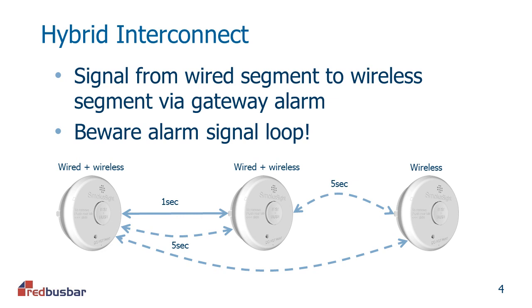However, for the wireless smoke alarm on the far right to sound, it's going to take about 5 seconds for it to receive the active alarm, and that's all fine. It will sound no problems. If at a later stage the originating alarm on the left-hand side stopped alarming, or the reason for it to alarm extinguished, for instance, then it would take a passage of time before the wireless alarm on the far right-hand side would stop sounding because of the transit times.